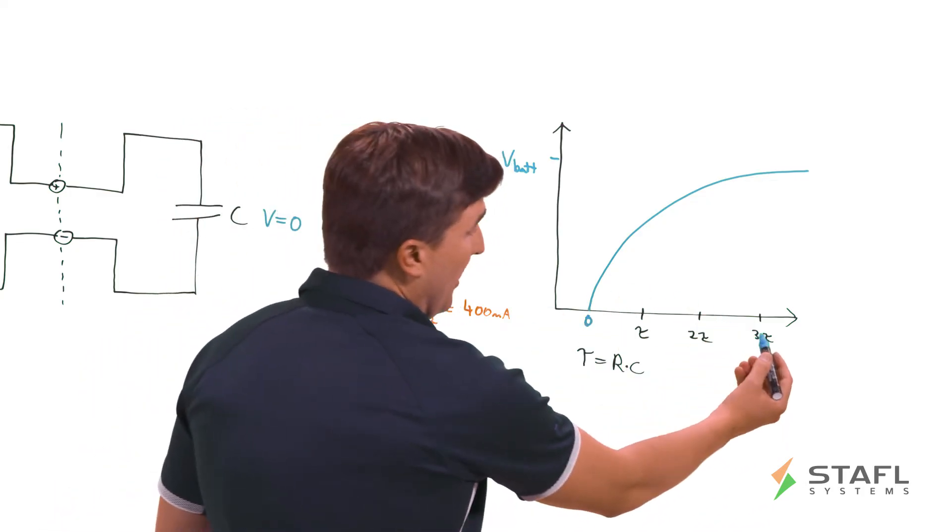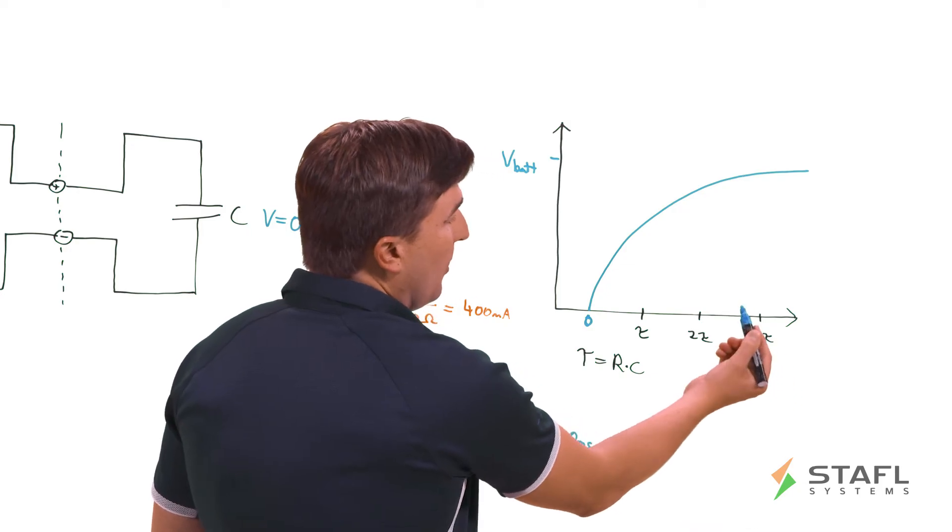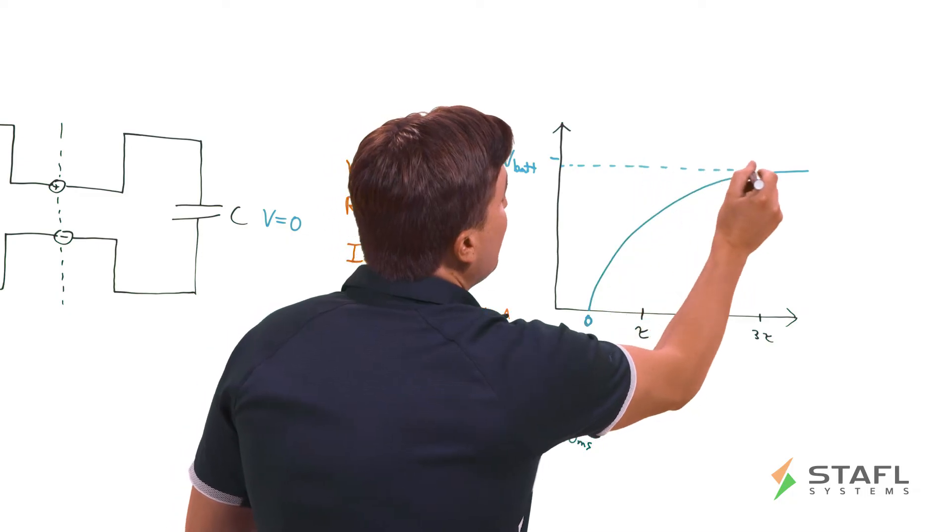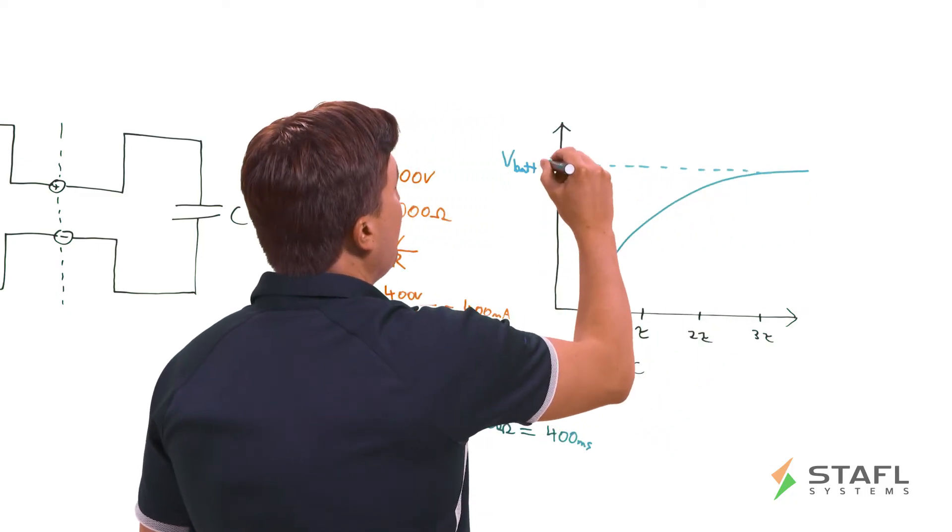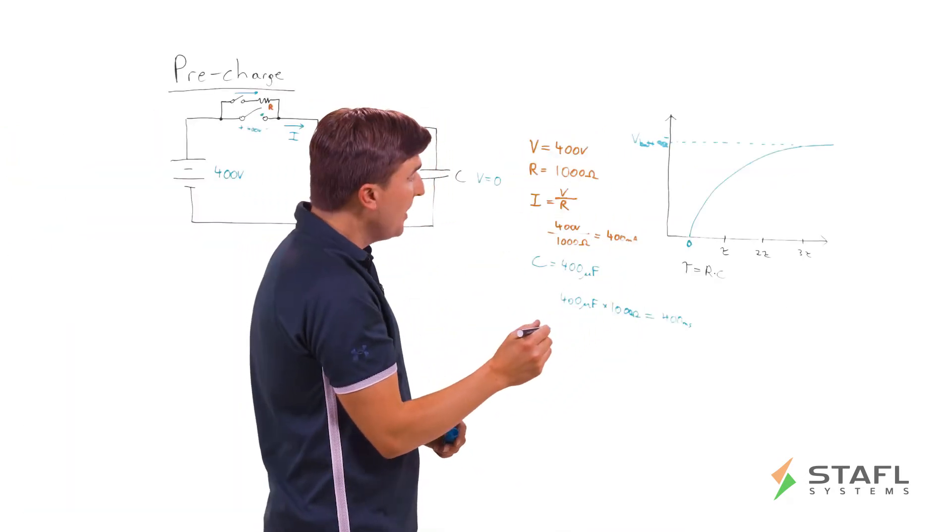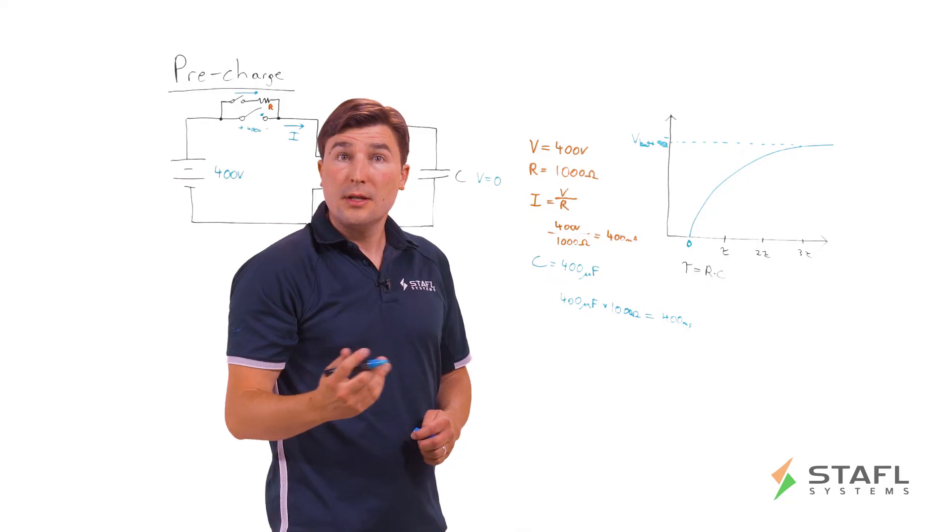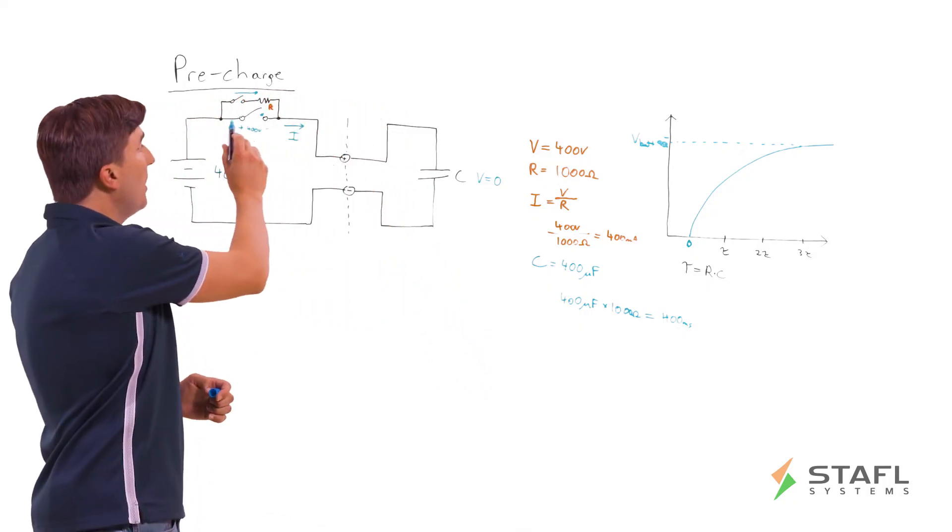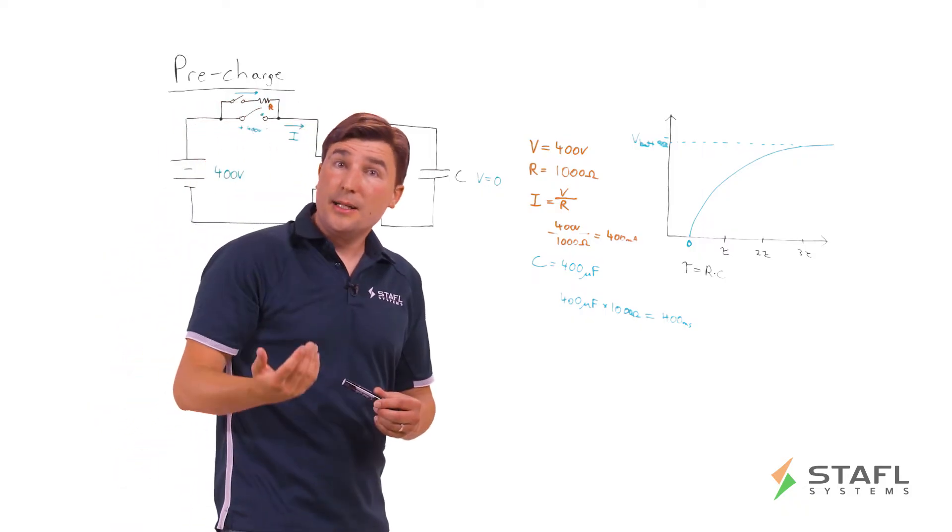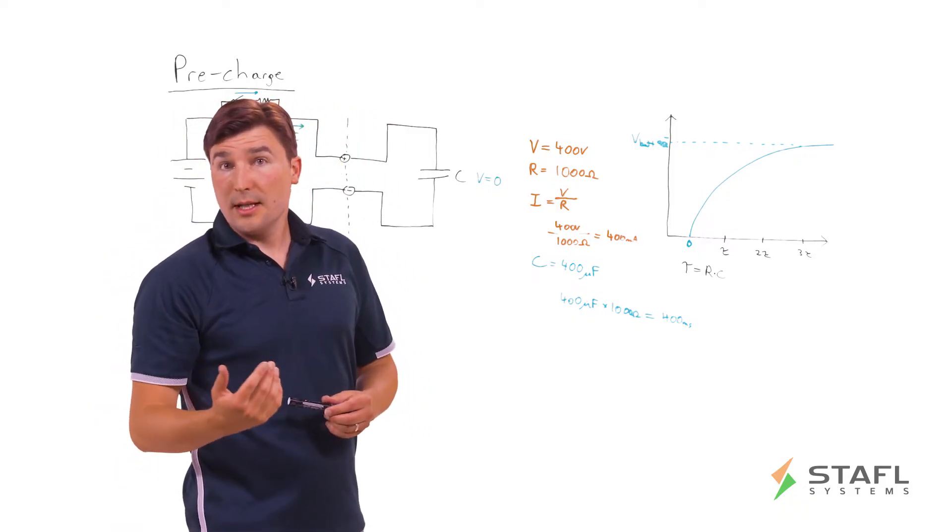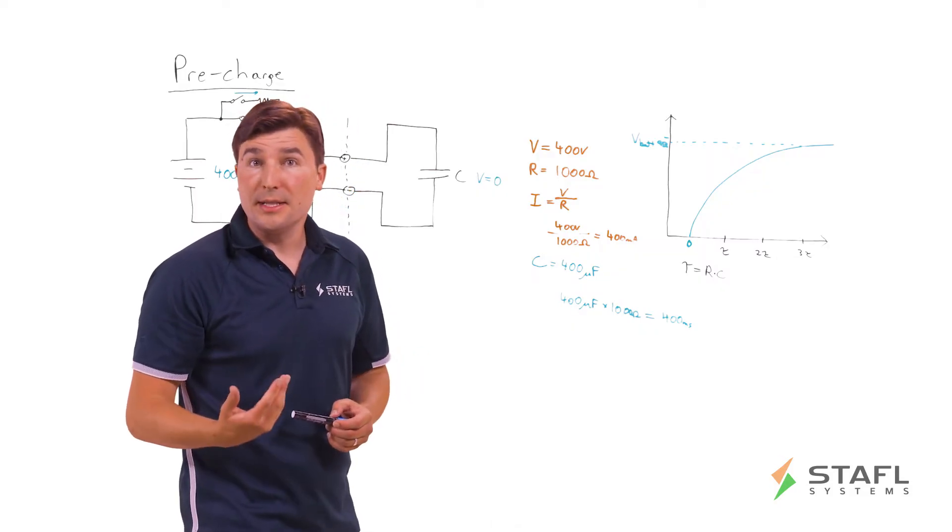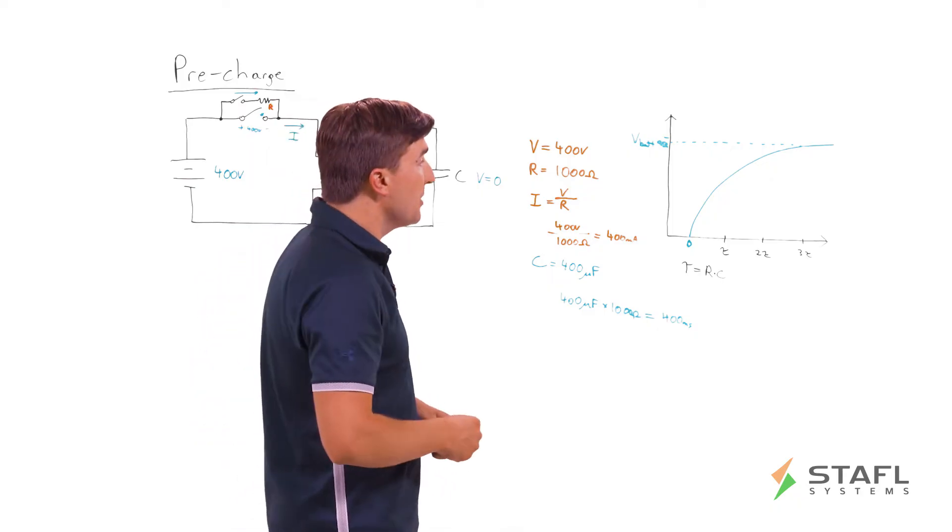So in this situation, we would expect that in 1.2 seconds, our voltage would be within 5% of the battery voltage. So in this case, 95% of the total battery voltage. And generally speaking, that is considered enough to close the main switch. Some systems you might want to select the threshold at 90% or 97%. There's some advanced calculations there. But generally speaking, three time constants or 95% is considered sufficient to close your main switch.